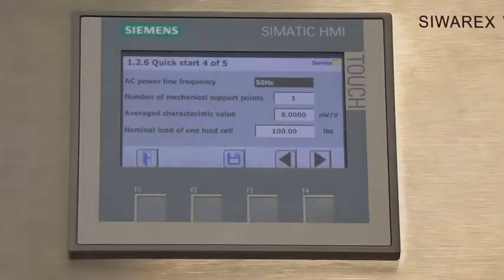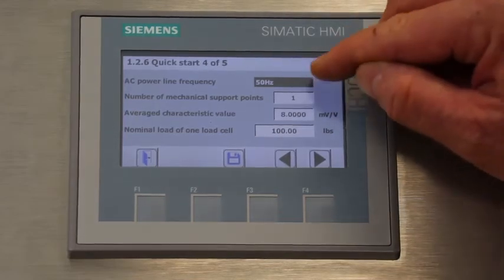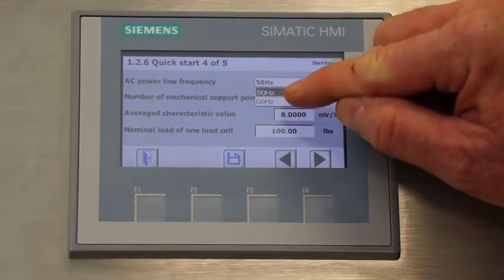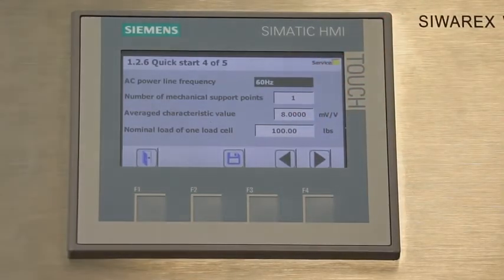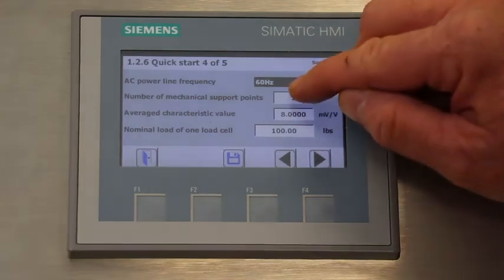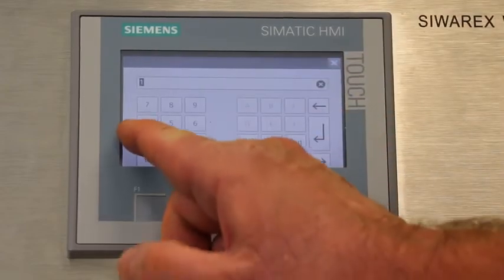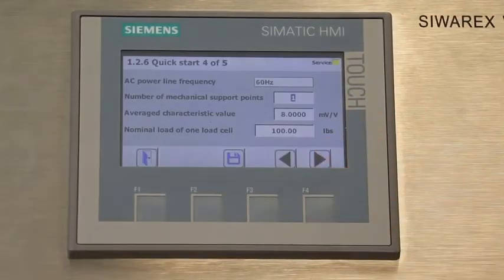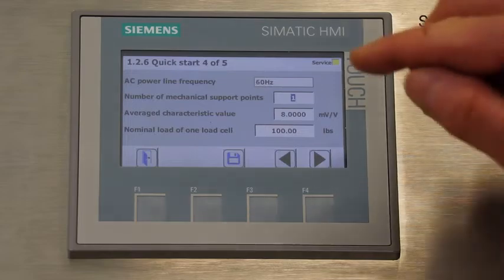The next screen will ask you several questions about the application of the load cell. The first question is the line power frequency. In the US, line power is at 60 Hz, so we'll select 60 Hz. The next question is the number of load cells in the application. Here we're using one load cell, so we'll enter a 1. The next field is the characteristic value. This is information that can be found on the data sheet of the load cell. I know that the characteristic value of this load cell is 1.9935, so I'll enter that.